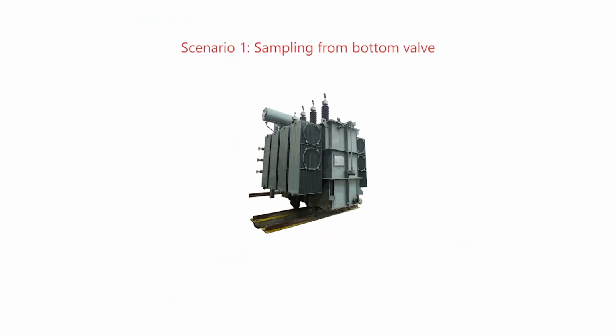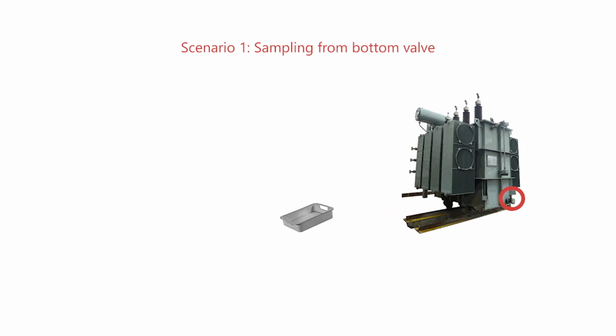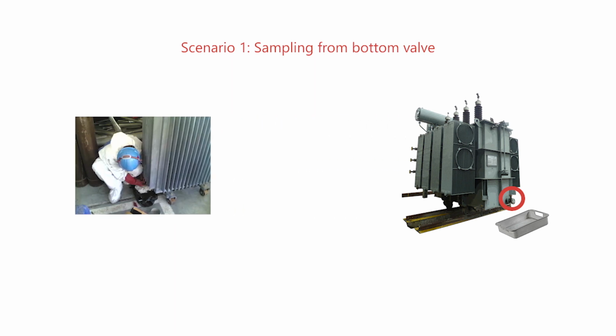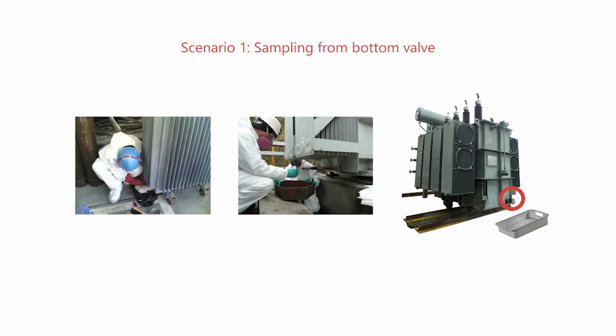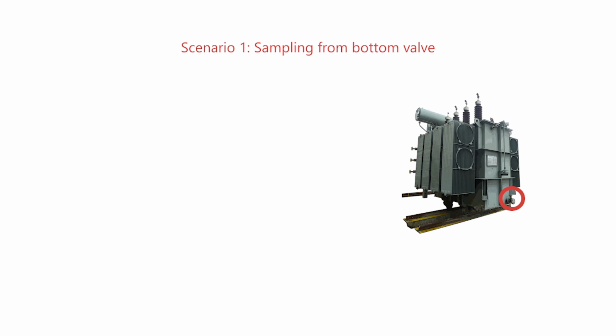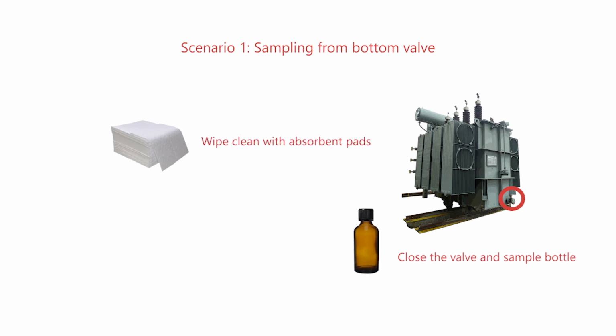Once the transformer has been made safe for sampling, identify the drain valve, located usually at the bottom of the transformer. One technician places a tray beneath the valve in case of spills or leaks, and opens the drain valve very slowly. Here it is important that the technician has both hands free to do this, while the other technician holds the sample bottle directly beneath the drain valve to collect 50 milliliters of oil. Now the drain valve and sample bottles are closed. Immediately swipe clean with absorbent pads.